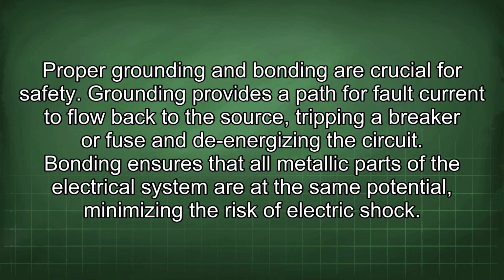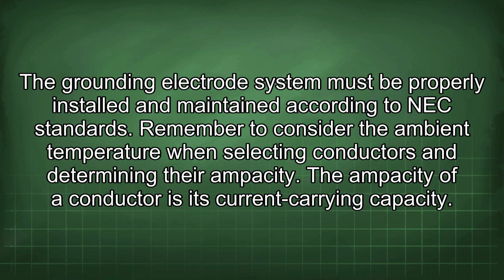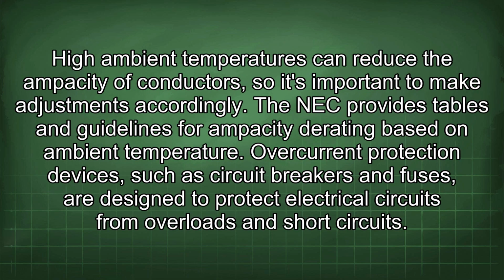Proper grounding and bonding are crucial for safety. Grounding provides a path for fault current to flow back to the source, tripping a breaker or fuse and de-energizing the circuit. Bonding ensures that all metallic parts of the electrical system are at the same potential, minimizing the risk of electric shock. The grounding electrode system must be properly installed and maintained according to NEC standards. Remember to consider the ambient temperature when selecting conductors and determining their ampacity. The ampacity of a conductor is its current carrying capacity. High ambient temperatures can reduce the ampacity of conductors, so it's important to make adjustments accordingly. The NEC provides tables and guidelines for ampacity derating based on ambient temperature.